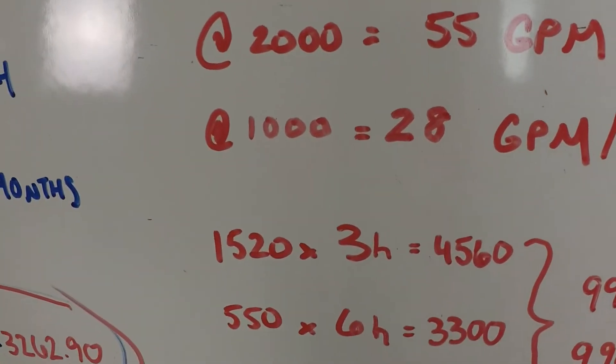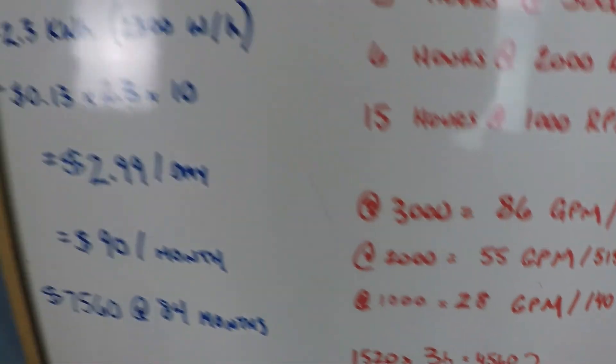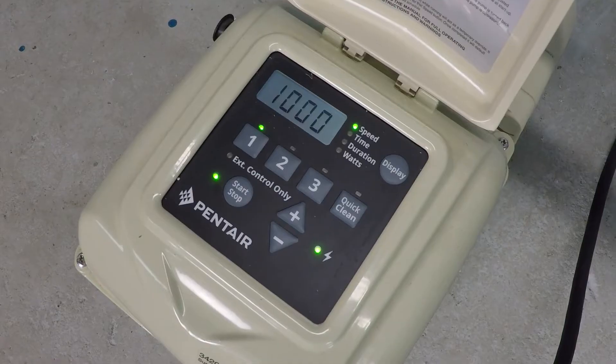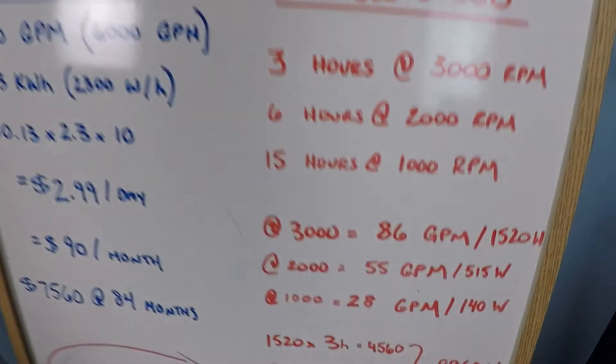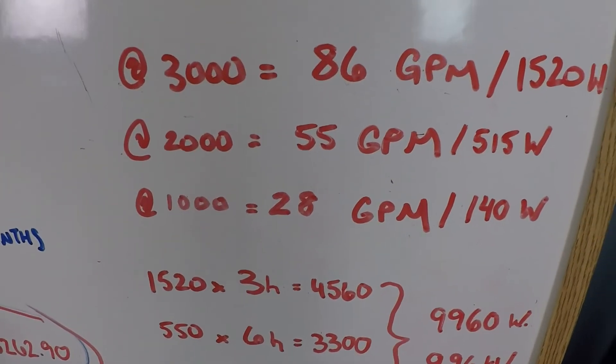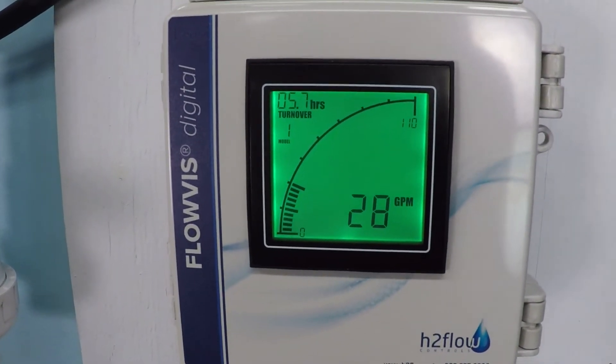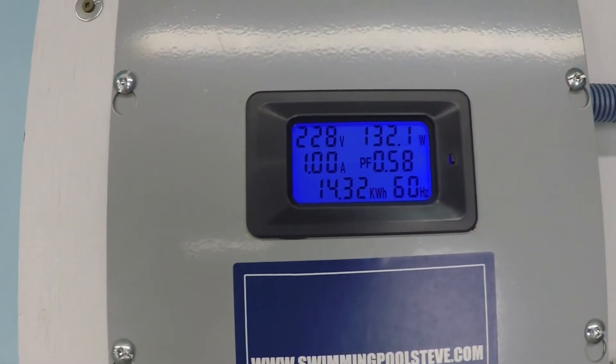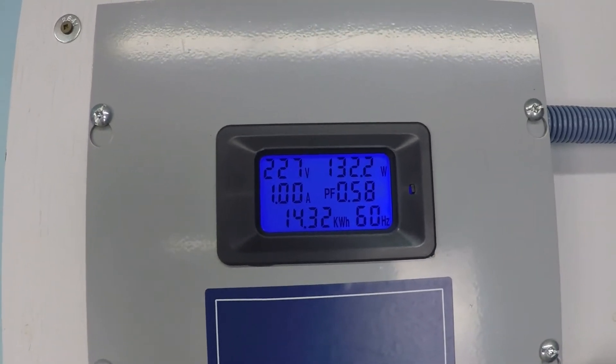And then we'll jump down to 1,000, and we should be seeing about 28 gallons per minute, and 140 watts. There we go. 28 gallons per minute. And we're even well under here. 132 watts, 1 amp even.